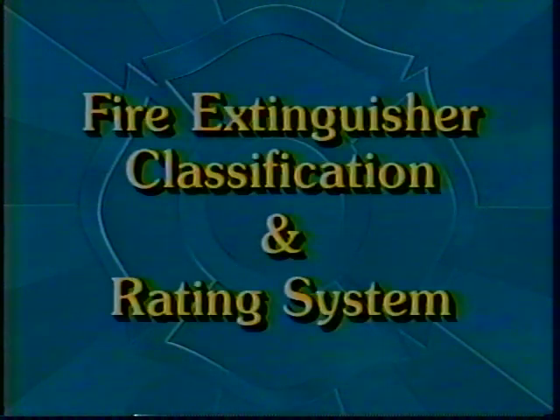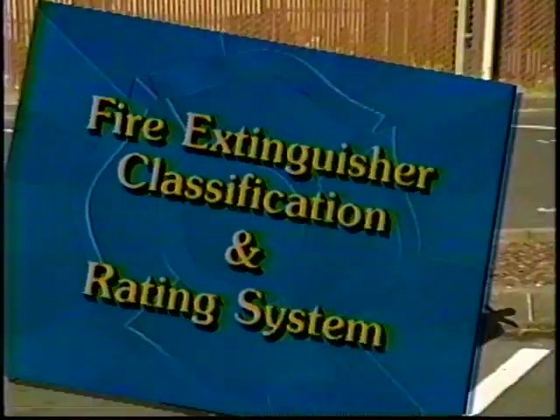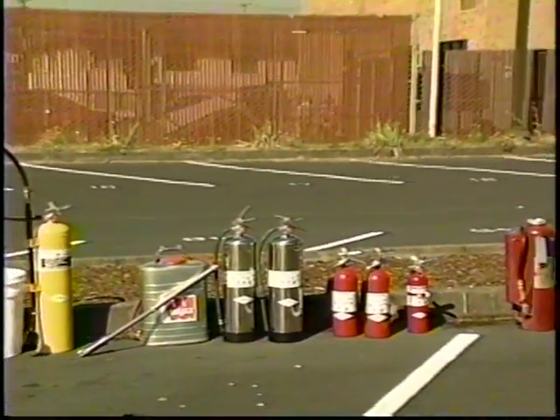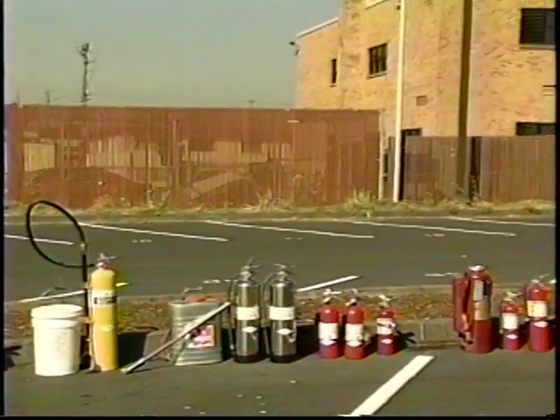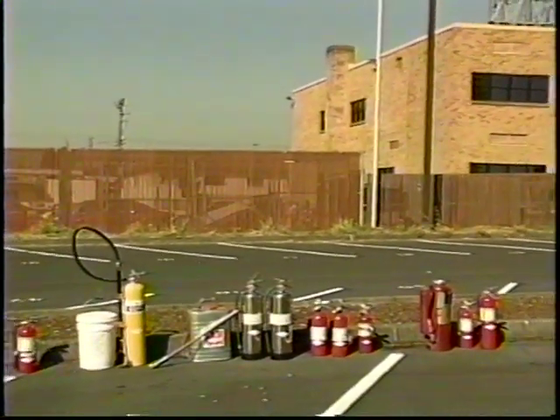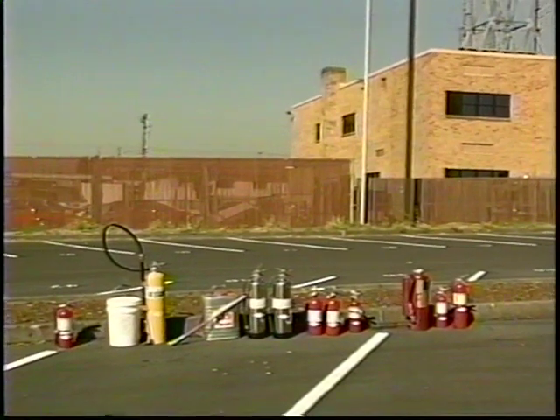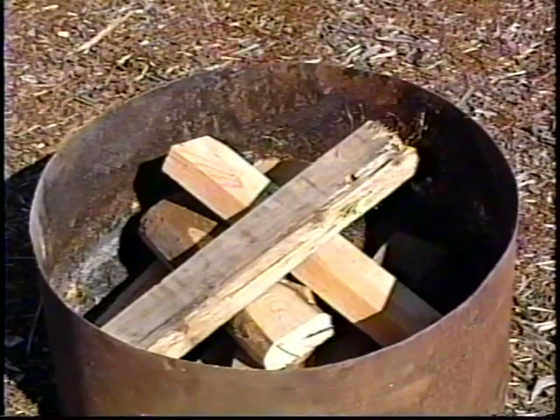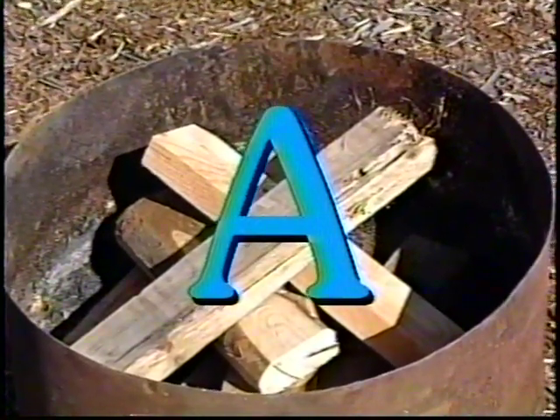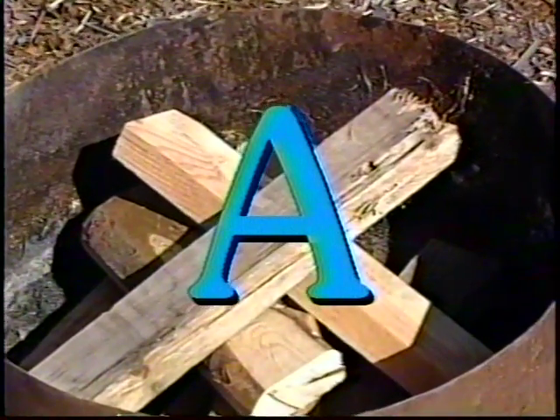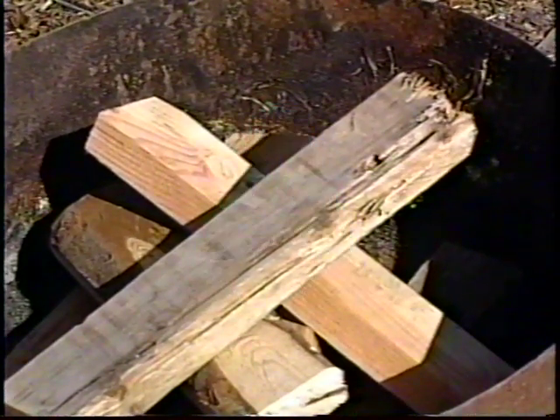To be able to recognize if you have the correct extinguisher for a fire, you need to know the classification and rating system used to identify fire extinguishers. The classification of fire extinguishers corresponds with the 4 classes of fire: A, B, C, and D. Class A fires involve ordinary combustibles such as paper, wood, cloth, and many plastics.